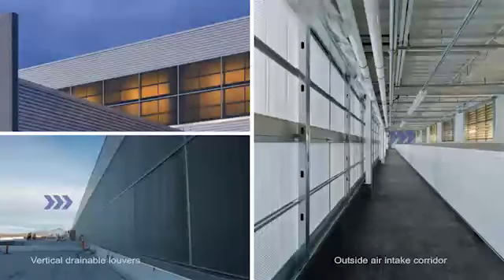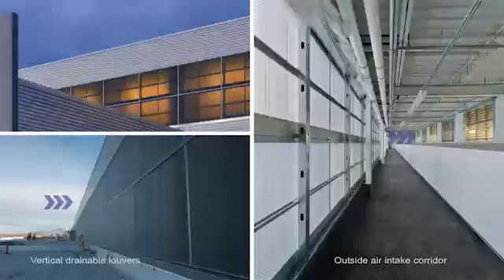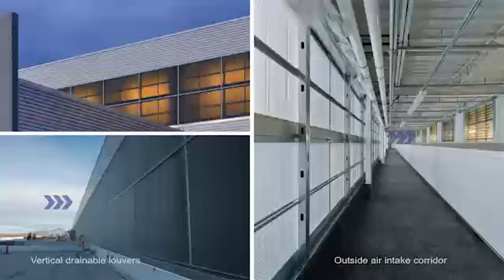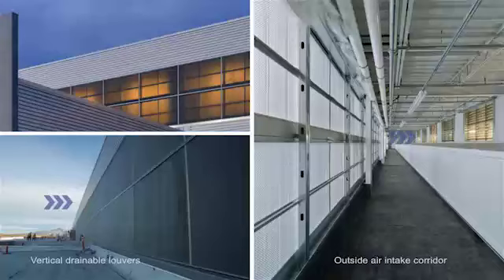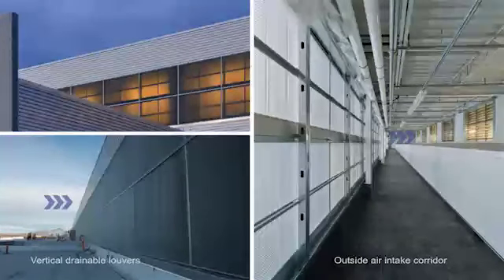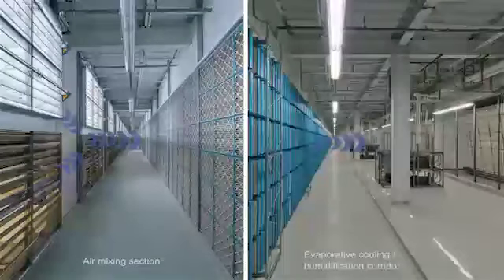So here's kind of a photo walkthrough of that system. We installed storm-proof louvers. The idea here is to remove any precipitation from the airstream as early as possible, but we still kind of created a wet zone. So we treated the intake plenum as roof. Here we do have floor drains to take care of any carryover that might make its way through the louvers. And you see on the right, those are the intake dampers drawing the air in, which are up on the left-hand side right now.